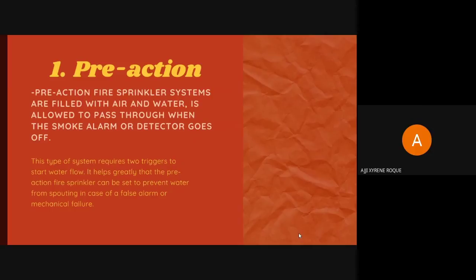Pre-action must operate and sprinkler head must fuse. This provides an added level of protection against inadvertent discharge, and for this reason, these systems are frequently employed in water-sensitive environments such as archive vaults, fine art storage rooms, rare book libraries, and computer centers.